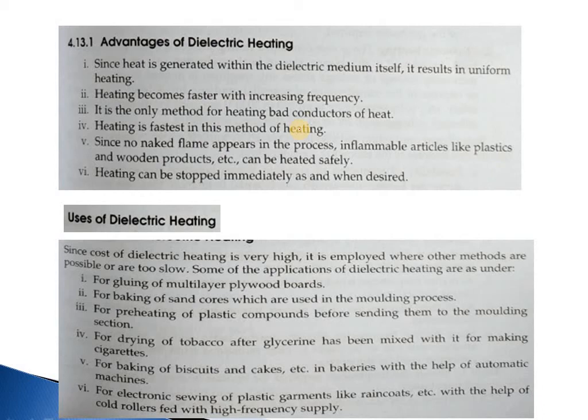Now we will see the advantages of dielectric heating. Six points are shown as advantages of dielectric heating. First, since heat is generated within the dielectric medium itself, it presents uniform heating. Secondly, heating becomes faster with increasing frequency. Third, it is the only method for heating non-conductors of heat. Fourth, heating is fastest in this method. Fifth, since no naked flame appears in this process, inflammable articles like plastic and wooden products can be treated safely. Sixth, heating can be stopped immediately when desired.